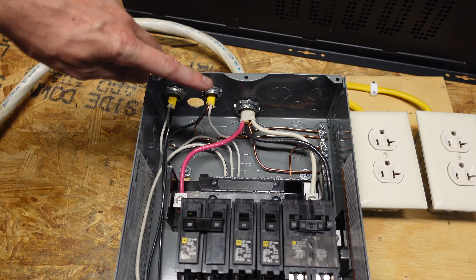So we can test loads on each of the two legs. I have a jumper installed between the ground bar and the neutral bar. I did these as two separate bars so I can remove this ground wire depending on what inverter I'm testing. I'm going to connect this breaker panel to my inverter with an old roll of 8-3 Romex. Here's how I made the connection with that number 8 wire before I close this panel up.